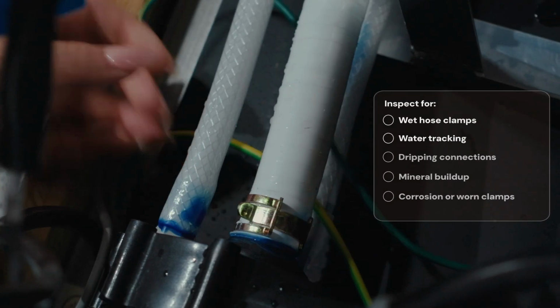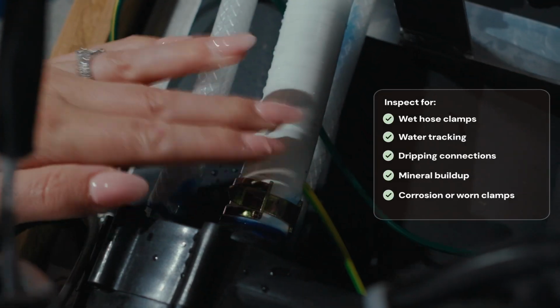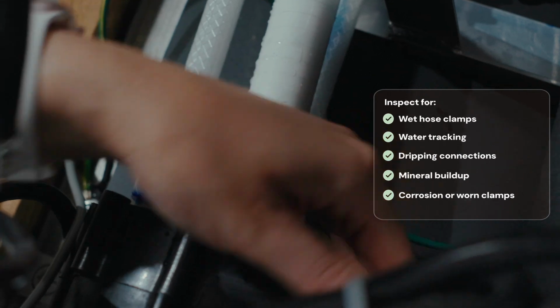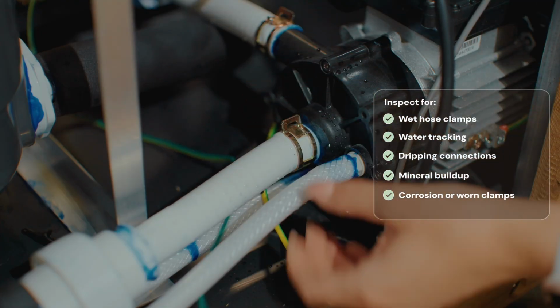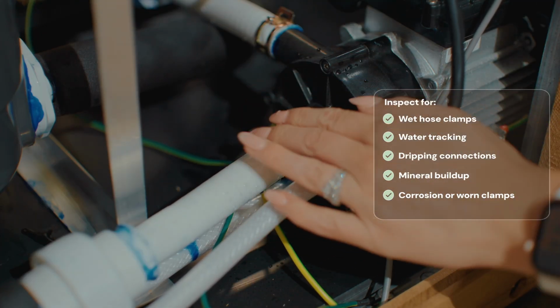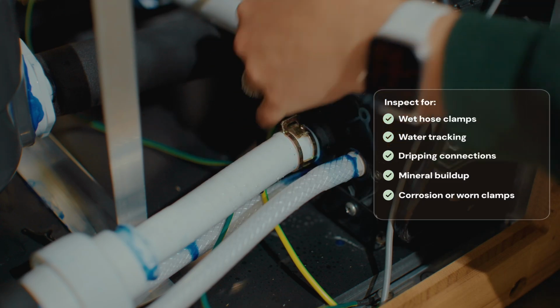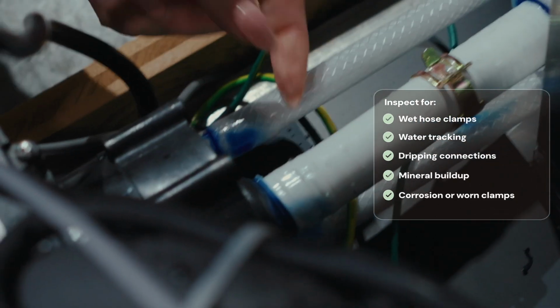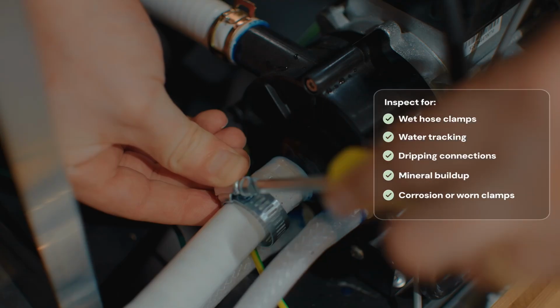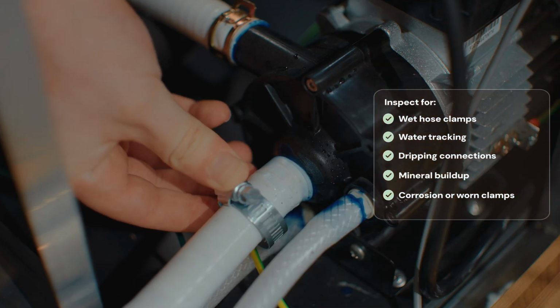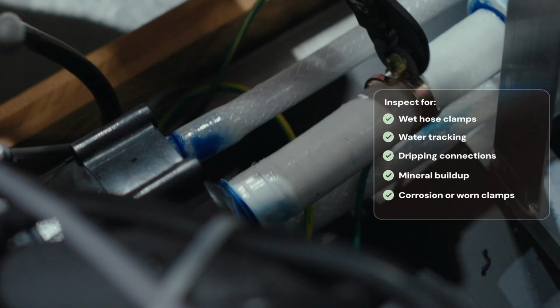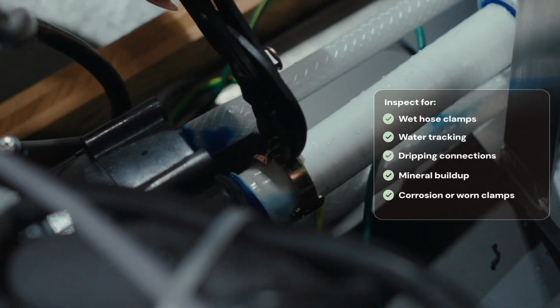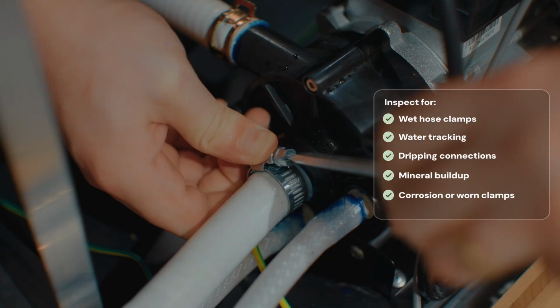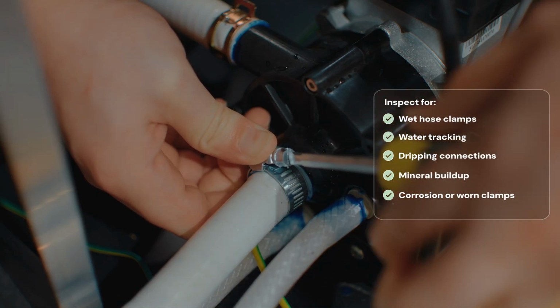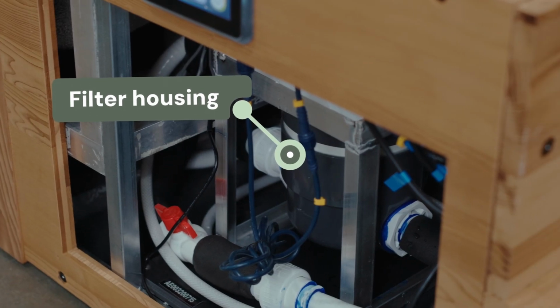Loose hose connection points are one of the most common causes of leaks. Carefully inspect all plumbing connections for moisture, loose clamps, corrosion, or signs of water tracking. Minor leaks are often resolved by tightening or repositioning the hose clamp. If the hose is improperly seated, disconnecting and reseating the connection may help create a better seal. If hose clamps appear heavily corroded, damaged, or worn, replacing the clamp may help restore a more reliable seal and prevent future leaks.